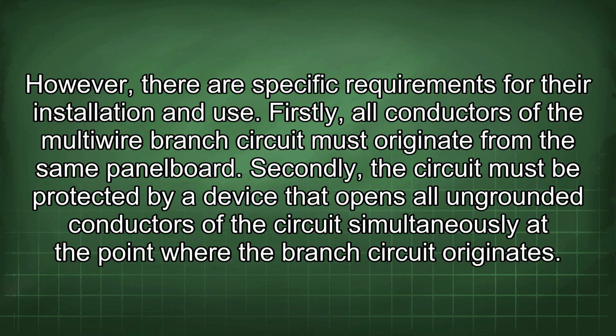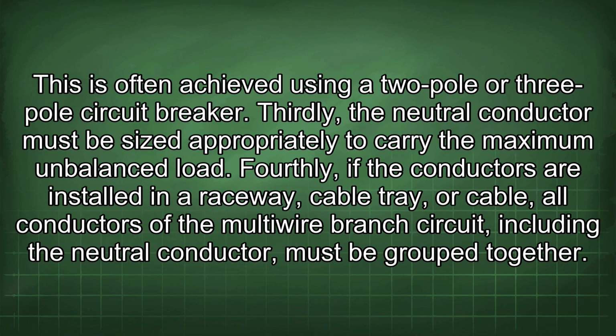Firstly, all conductors of the multiwire branch circuit must originate from the same panel board. Secondly, the circuit must be protected by a device that opens all ungrounded conductors of the circuit simultaneously at the point where the branch circuit originates. This is often achieved using a 2-pole or 3-pole circuit breaker. Thirdly, the neutral conductor must be sized appropriately to carry the maximum unbalanced load. Fourthly, if the conductors are installed in a raceway, cable tray, or cable, all conductors of the multiwire branch circuit, including the neutral conductor, must be grouped together.